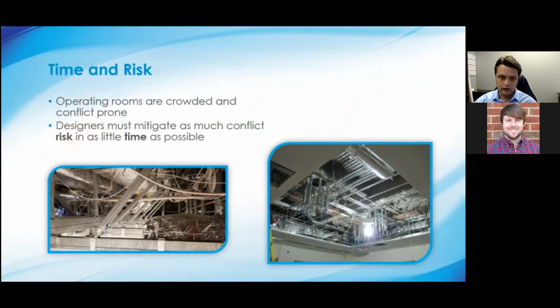Now, the construction side of this is a little bit trickier. Operating rooms are crowded and very conflict prone. Almost every device wants to be close to the table, especially in the ceiling, you have air, booms, med gas, lights, structural components all trying to be as close as possible. The designer's role is to mitigate that conflict risk efficiently, getting design hours in without going over budget while minimizing risk.